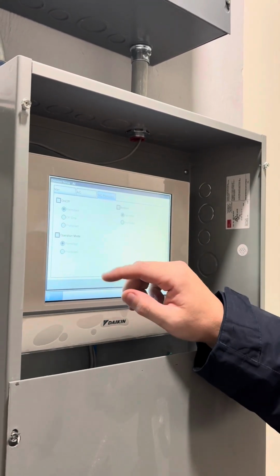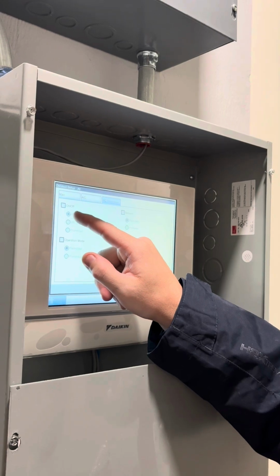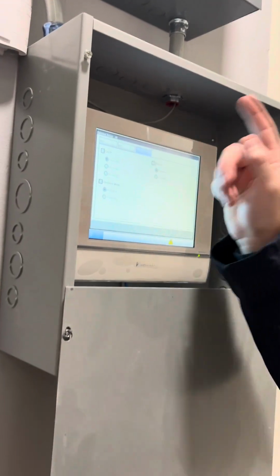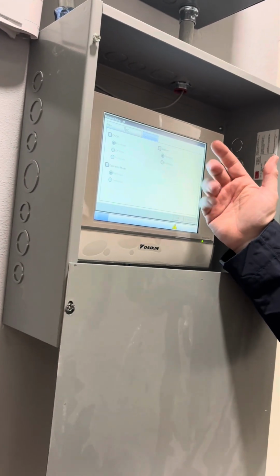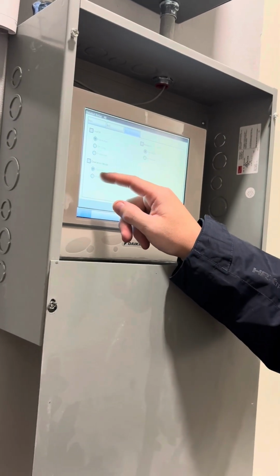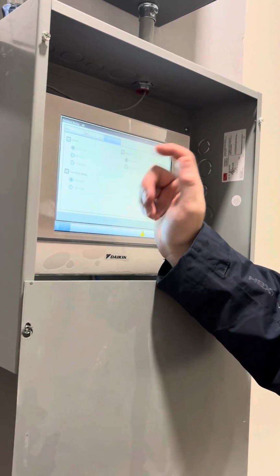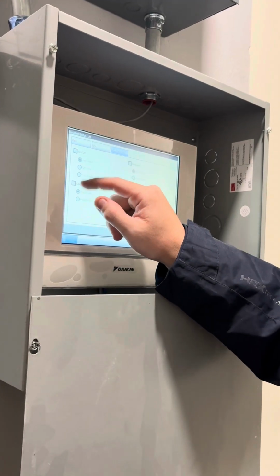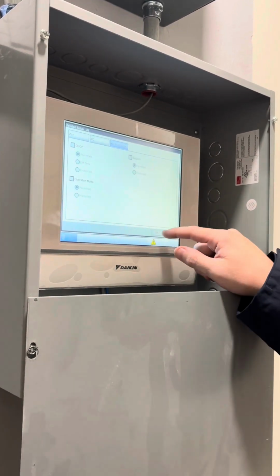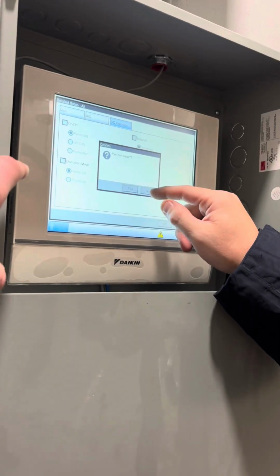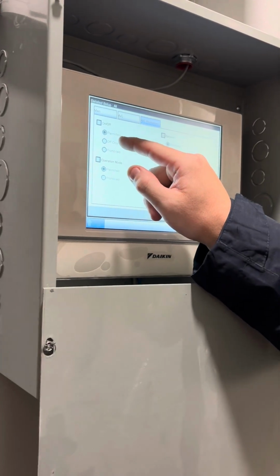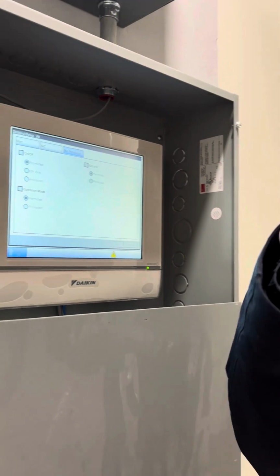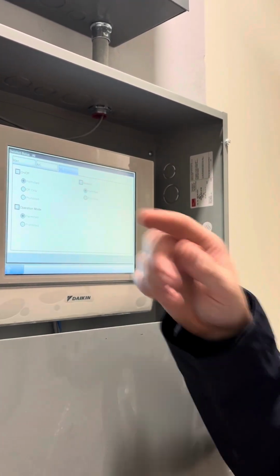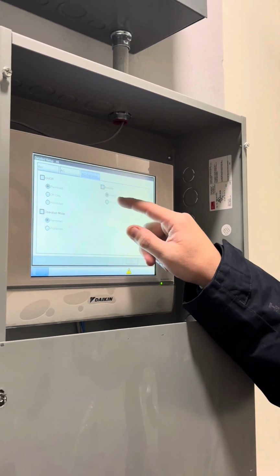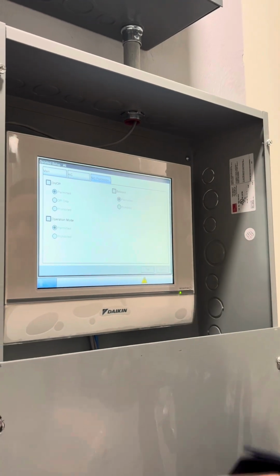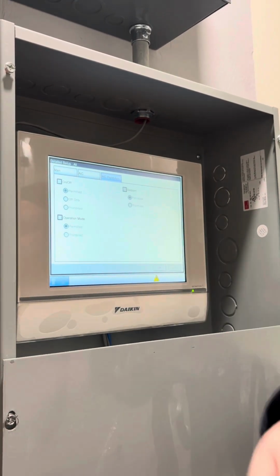This RC prohibit is if you can allow them to change set points. You want them to be able to change set points. Maybe not necessarily, depending on how you're working it, change operation modes and on/off permit. So most of those are okay. Permitted means we are allowed to change. Permit means that for the thermostat, you're giving them permission to turn it on and off, permission to change the set point, and permission to change the mode.